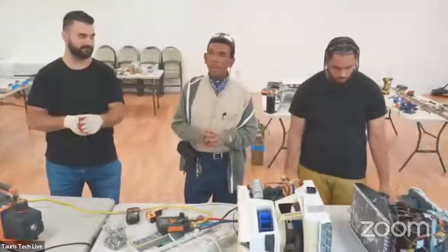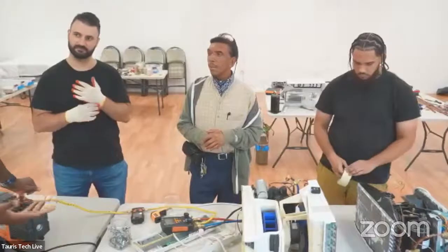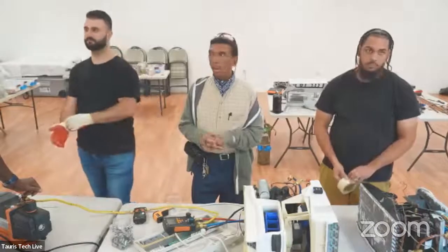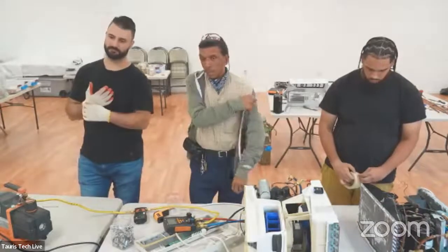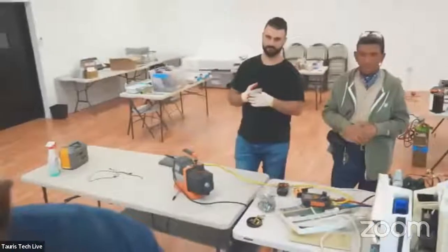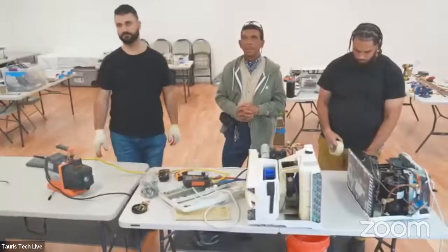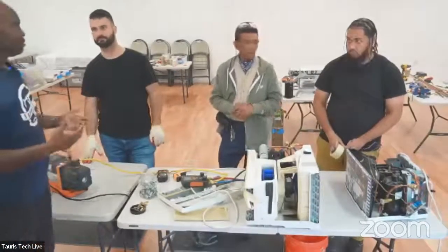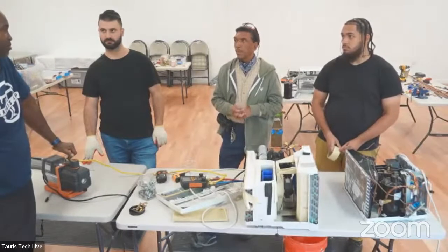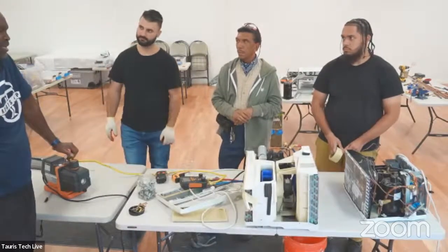Isn't it more work shipping a system like that? Okay. Well, it's work, but it's work for the people who are getting paid to be there, so they don't care. Essentially, we'll talk more about absorption soon, but the reason they use absorption is because the only thing you need is heat in the generator. If you have some type of heat that you can run in your generator, then essentially you're getting cooling for free. So you'll find it in a lot of industrial plants where you have some type of free heat source. But yeah, it's considered green.